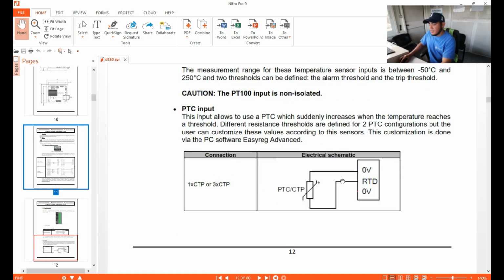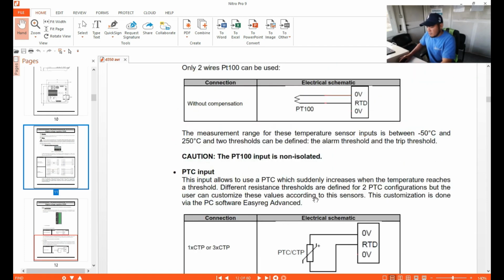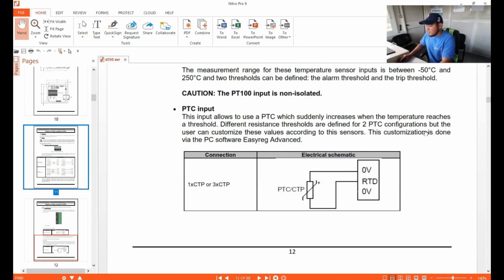Okay, next is your PTC CP. This one is also 0 to RTD. If I read it here, the temperature measurement reference to the temperature input is -50 to 250 degree thresholds. So here, the PTC configuration can customize these values according to this sensors, created with the Easy Rig software.